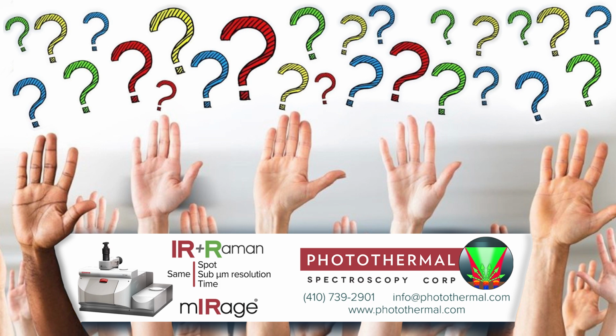But with OPTIR, we detect the signal through monochromatic light, a single wavelength of green. And so there is no wavelength-dependent scattering. It's constant, hence the spectrum isn't affected by the roughness like a regular FTIR would be, as long as it's focused well, of course. That's my long-winded but somewhat passionate answer, because I feel strongly about this point.